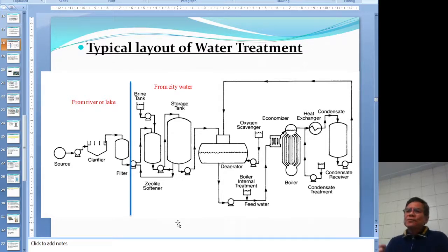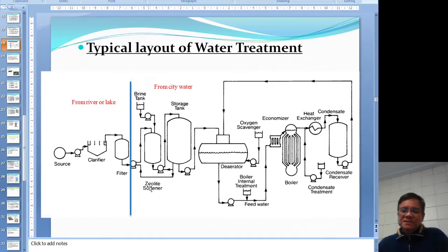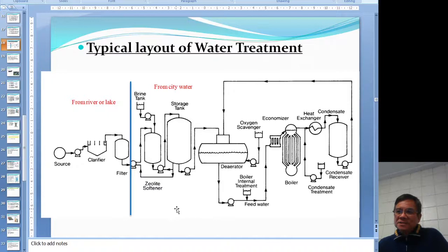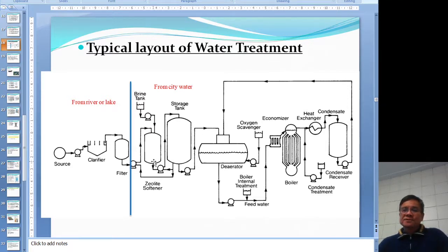After this, you go into the sodium zeolite softener. After treatment, you put the water into a storage tank. In that storage tank you might add some chemicals to adjust the pH. The water in the storage tank is called makeup water. Instead of the sodium zeolite softener you can put a reverse osmosis unit in there to replace it.